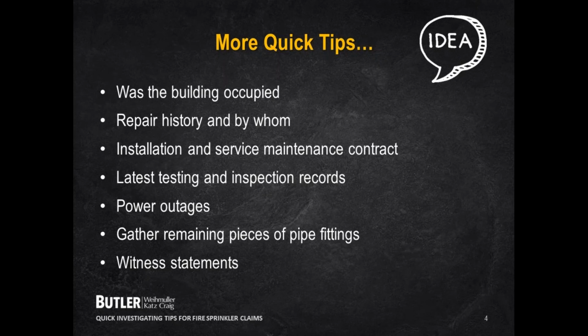And gather the remains of pieces of pipe fitting. That's going to be critical for a fire protection engineer to inspect. A lot of times we will work really hard on trying to find these broken pieces, and the earlier the better that you can inform the insured to not throw anything away. It may look like garbage, but it's precious evidence to us.